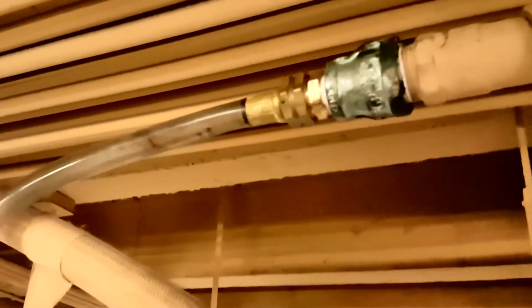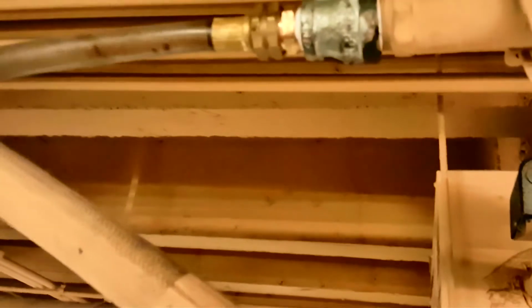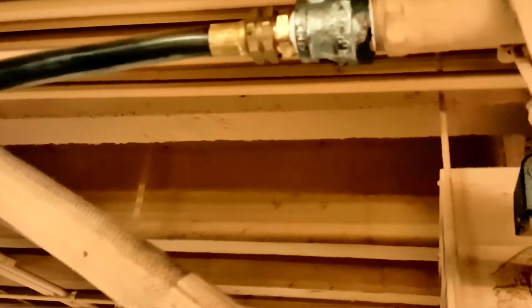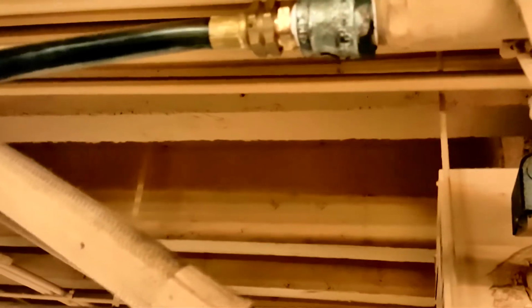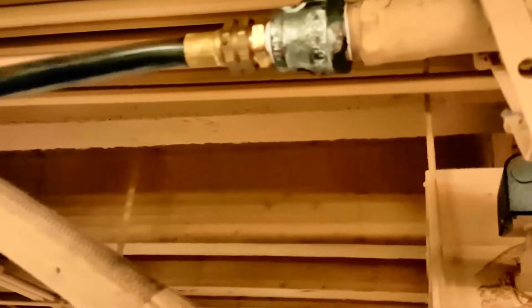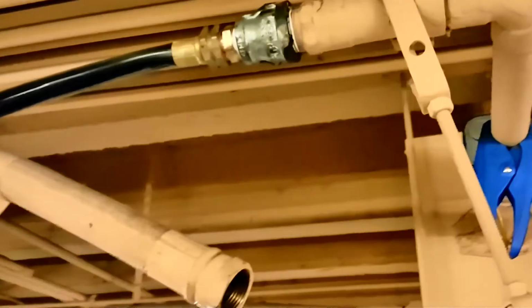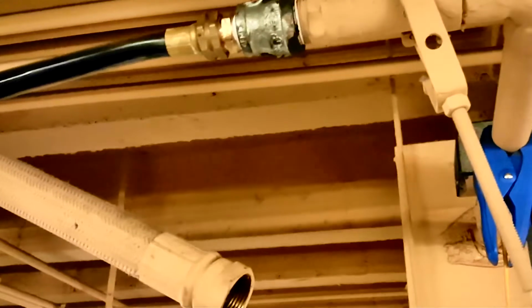And you can hear the pump is struggling to pump chemical through the system. In fact, a couple of times that we've done it already, the pump was shut off for a second because there's just too much pressure basically. We're going to be spraying the chemical in. We're going to leave it here for about an hour.